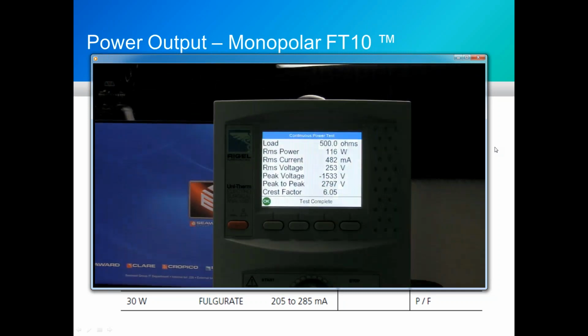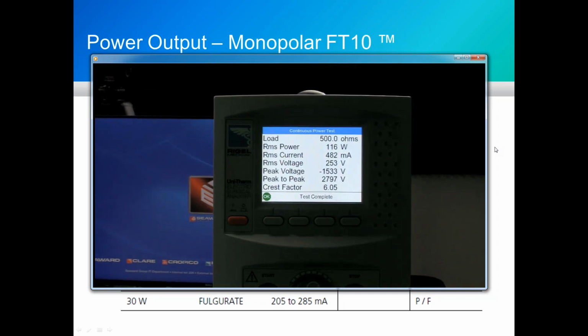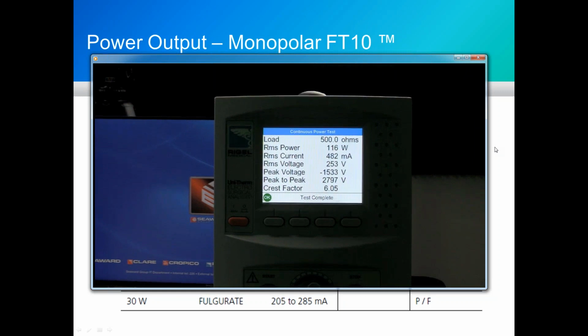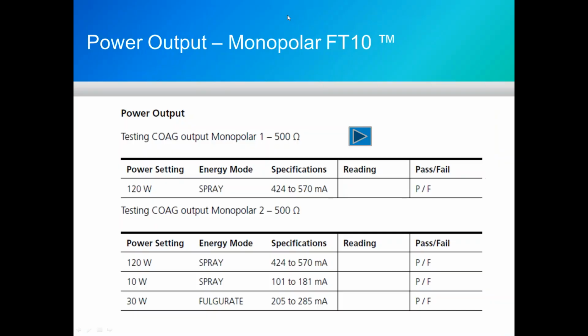So I had a test of 5 seconds on, 5 seconds off, and there you see the true RMS current that we measured, because again we have an internal current transformer. And with the Covidien products, you do pass/fail based on the current reading. And there is the CoAG test on monopolar 1.